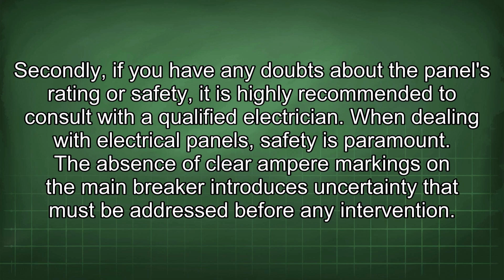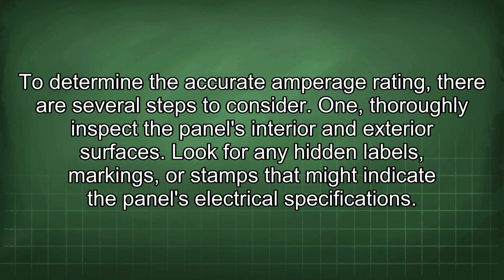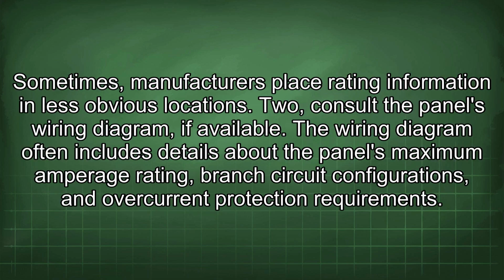The absence of clear ampere markings on the main breaker introduces uncertainty that must be addressed before any intervention. To determine the accurate amperage rating, there are several steps to consider. 1. Thoroughly inspect the panel's interior and exterior surfaces. Look for any hidden labels, markings, or stamps that might indicate the panel's electrical specifications. Sometimes manufacturers place rating information in less obvious locations.